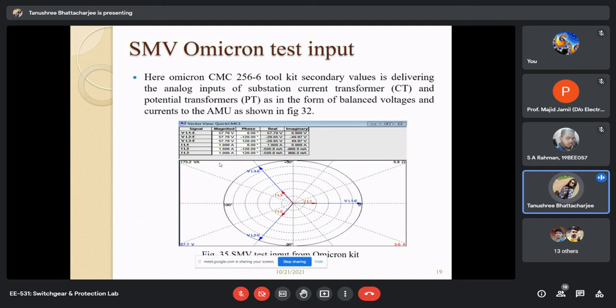The merging unit actually has a TRM, turns ratio multiplier, inside it. When we input 100 volt and 1 ampere from Omicron, we have set its ratio as 2200:1 and 1000:1, so that it converts and transfers as 220 kV and 1 kilo ampere to the IED. And 57.7 is because we divided 100 by √3 to get phase values.